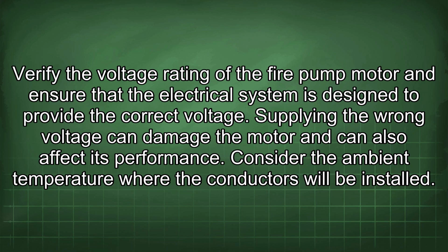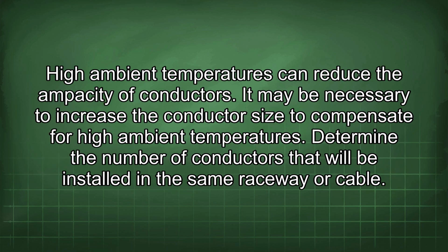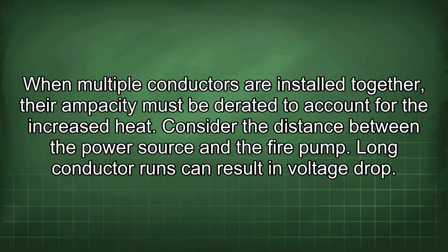Consider the ambient temperature where the conductors will be installed. High ambient temperatures can reduce the ampacity of conductors. It may be necessary to increase the conductor size to compensate for high ambient temperatures. Determine the number of conductors that will be installed in the same raceway or cable. When multiple conductors are installed together, their ampacity must be derated to account for the increased heat.